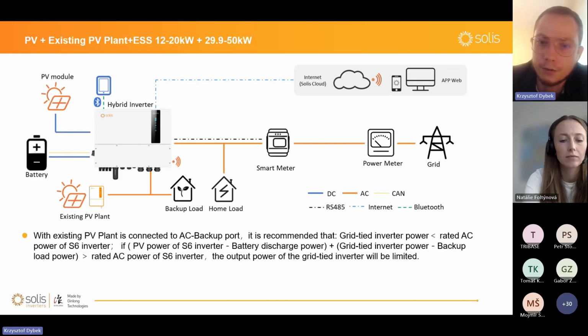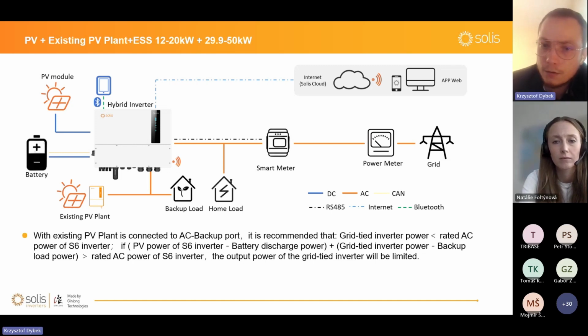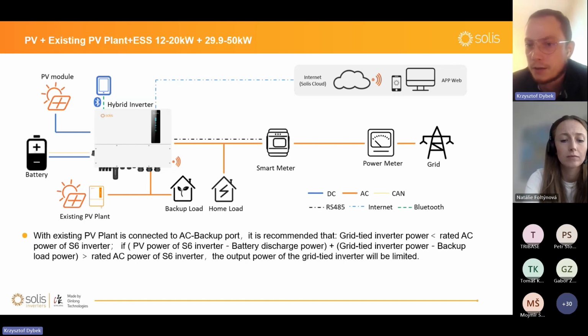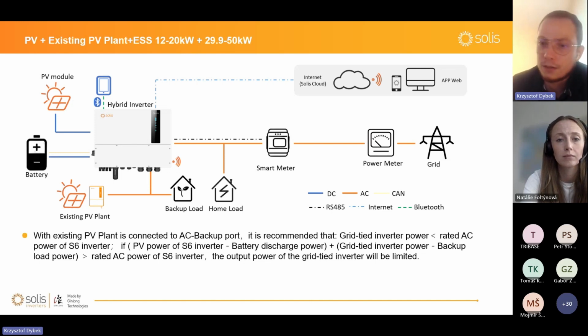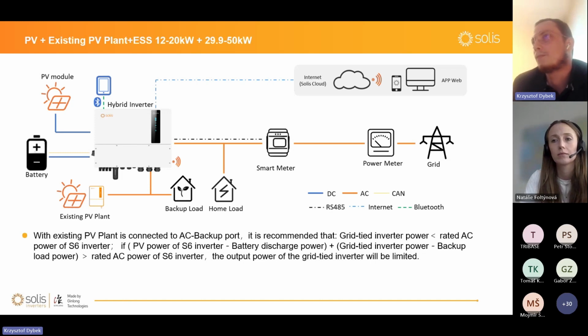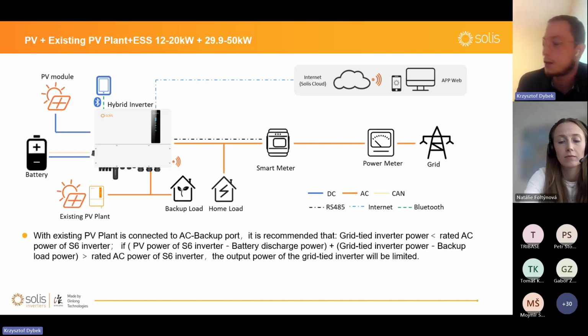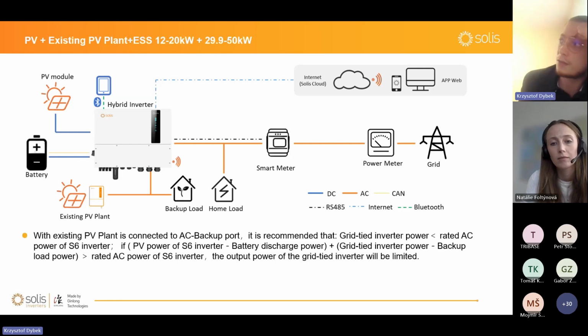The start, stop, and power control of the grid-tied inverter are realized by adjusting the frequency of the backup output. So the working logic is that the PV hybrid plus the existing PV power the load and then charge the battery until the battery reaches the off SOC. The system will then reduce the output power of the grid-tied inverter to 0. Off SOC you can set, for example, at 100% or 90%. Then the PV inverter will shut down because it will get something like an over-frequency alarm, because the frequency will increase, starting at 50 hertz, then 51, 52, and after 52 there is over frequency. End of story. That's it.